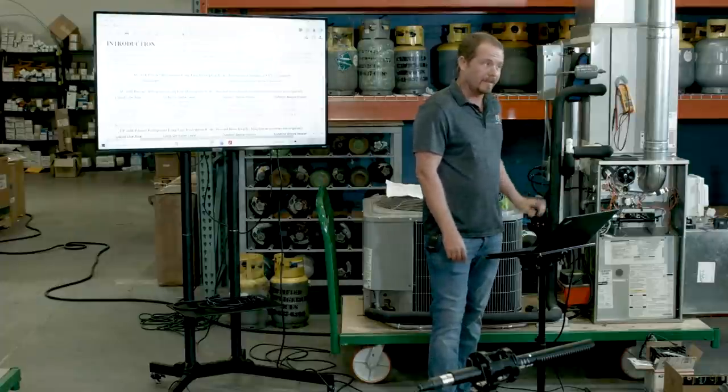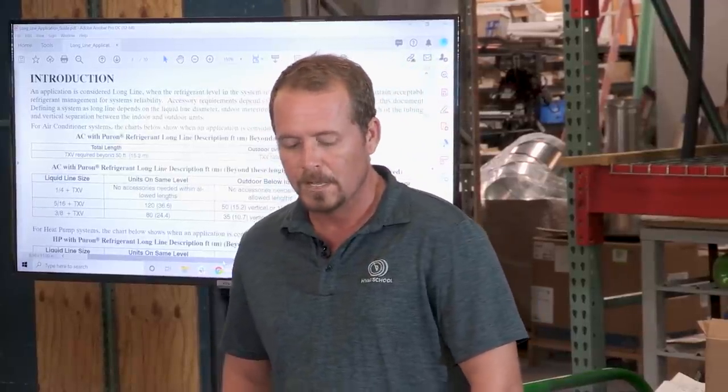True. What do they call that? What's the term that at least Carrier uses for it? Hard shut off, HSO, right? Another term for it is non-bleed. So you can describe it a couple different ways. You have a bleed valve, you have a non-bleed valve, also known as a hard shut off. Or you could call the bleed valve a non-hard shutoff. So many names. But the reason why the TXV hard shuts off is just simply how TXVs work.